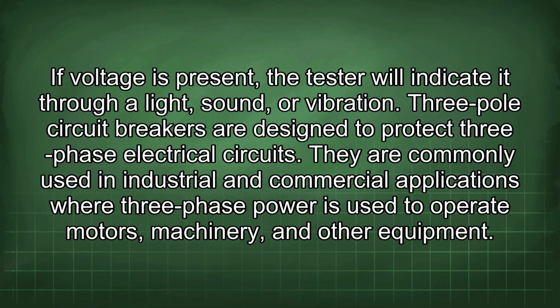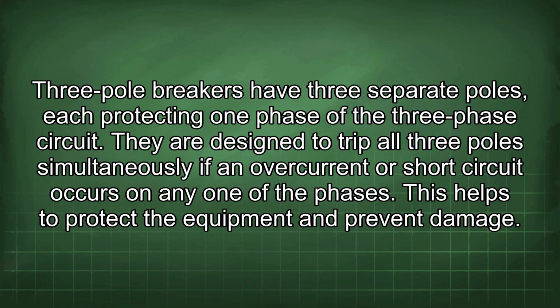Three-pole circuit breakers are designed to protect three-phase electrical circuits. They are commonly used in industrial and commercial applications where three-phase power is used to operate motors, machinery, and other equipment. Three-pole breakers have three separate poles, each protecting one phase of the three-phase circuit. They are designed to trip all three poles simultaneously if an overcurrent or short circuit occurs on any one of the phases. This helps to protect the equipment and prevent damage.